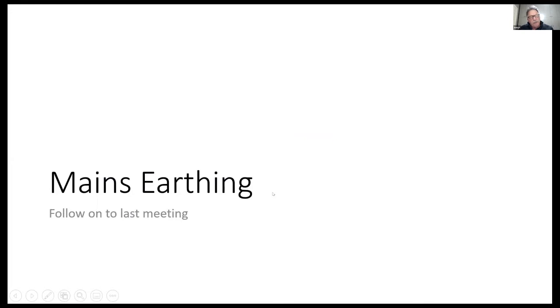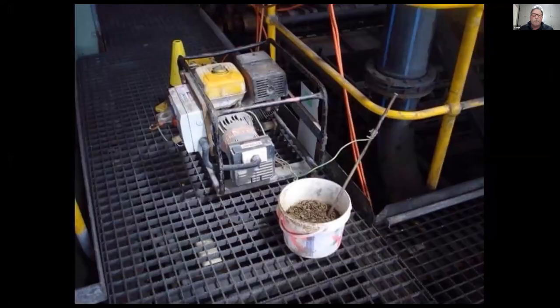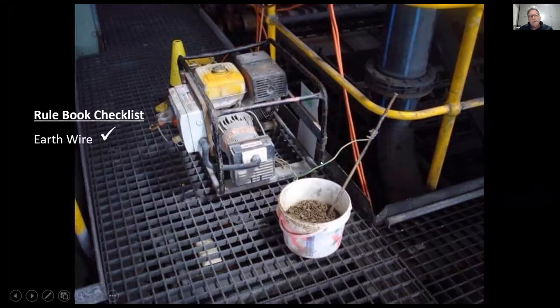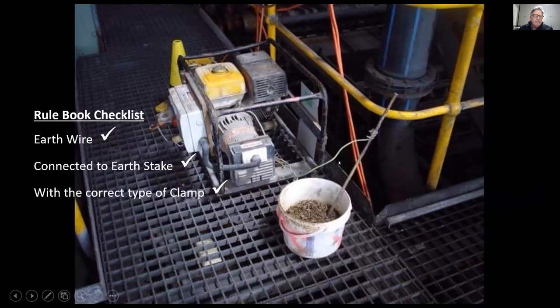Starting on mains earthing, I thought I'd start with an example of a portable generator, and let's pull out the rule book and check whether it's properly earthed. It's got an earth wire, green-yellow, connected to an earth stake, with the right type of clamp, and it's inserted into some soil - looking pretty good. Well, what else do we want?